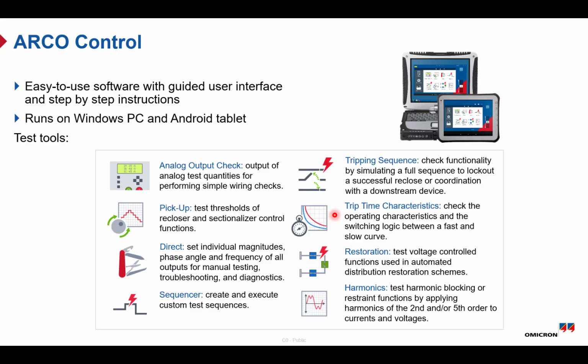The trip time characteristic tool is used to verify protection curves and timing, including fast and slow curve behavior. The restoration tool is used for testing voltage-based functions, especially in automation schemes. And finally, the harmonics tool is used to test how the controller responds to harmonic content such as the second or fifth harmonic, especially if the load has a distribution low voltage transformer, which might lead to the inrush phenomenon. So overall, this module gives you everything you need to perform both basic and advanced testing in a structured and efficient way.